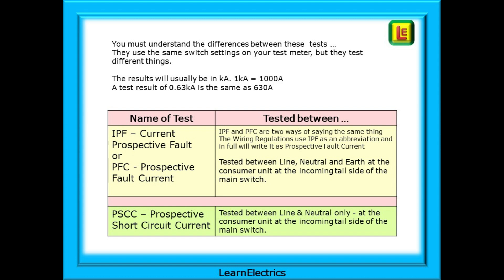PSCC, Prospective Short Circuit Current, is tested between line and neutral only at the consumer unit at the incoming tail side of the main switch. It tells us how much current will flow if there is an electrical short between the line and neutral conductors. And notice there is no mention of earth in a short circuit test.